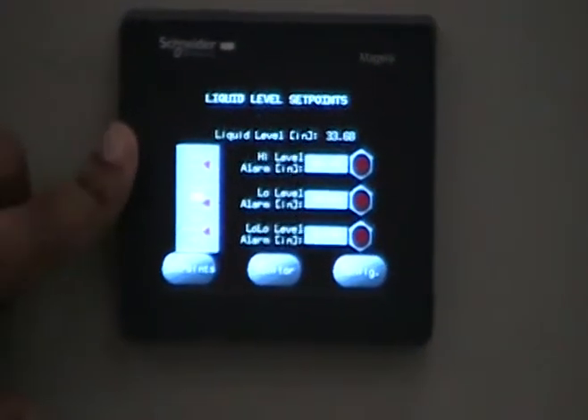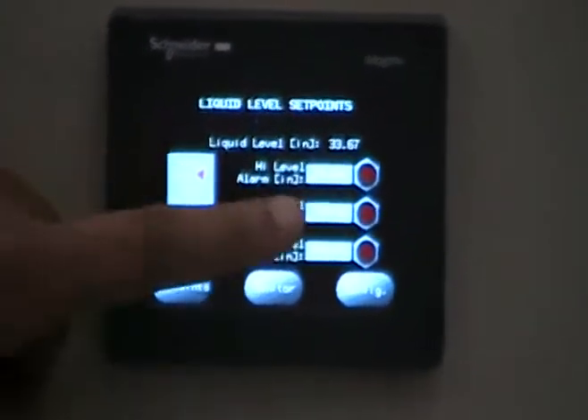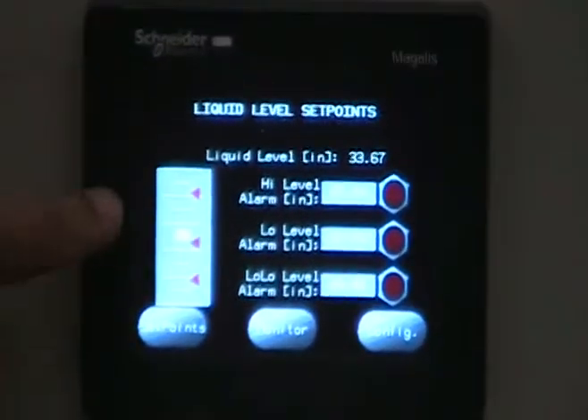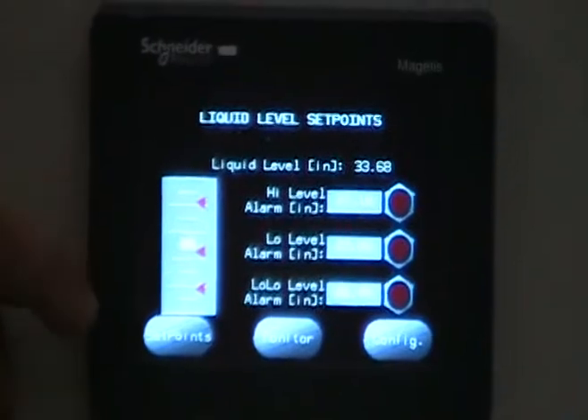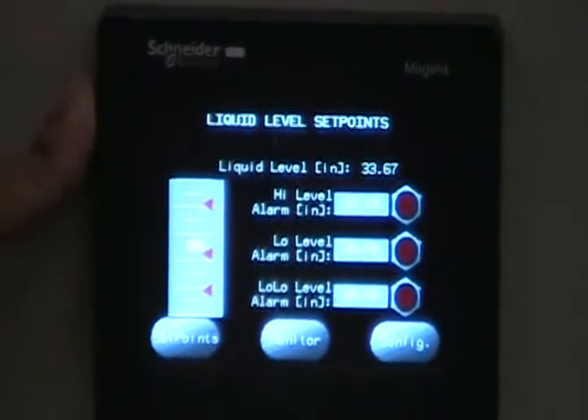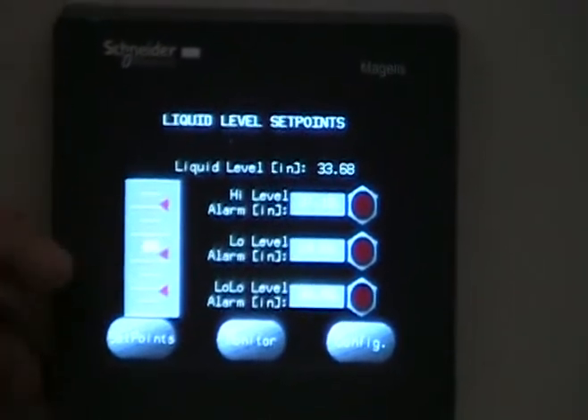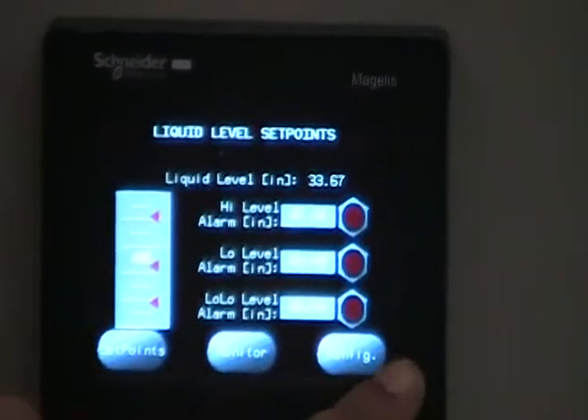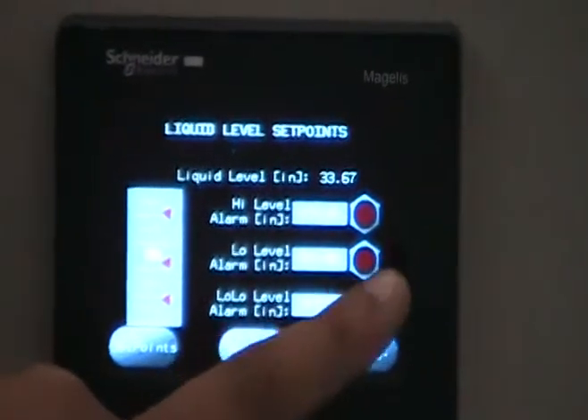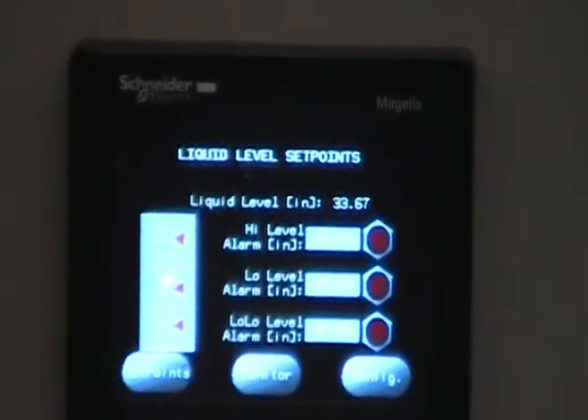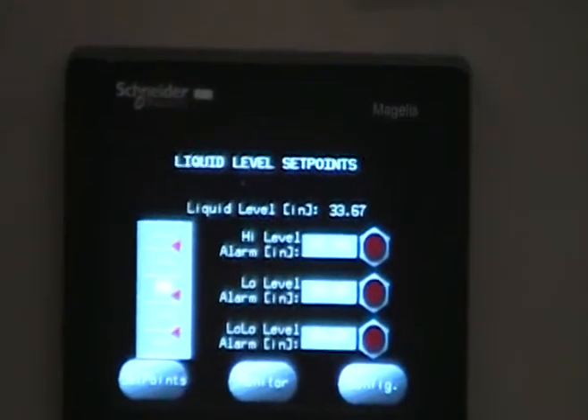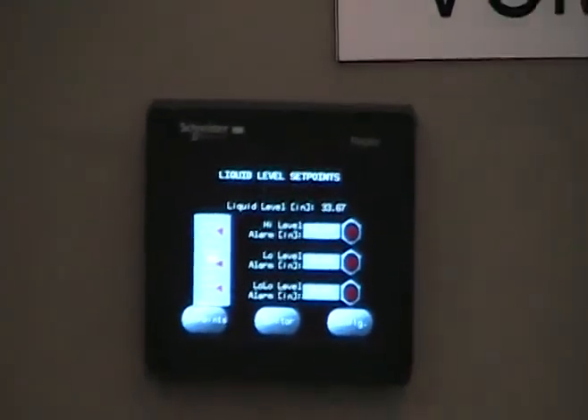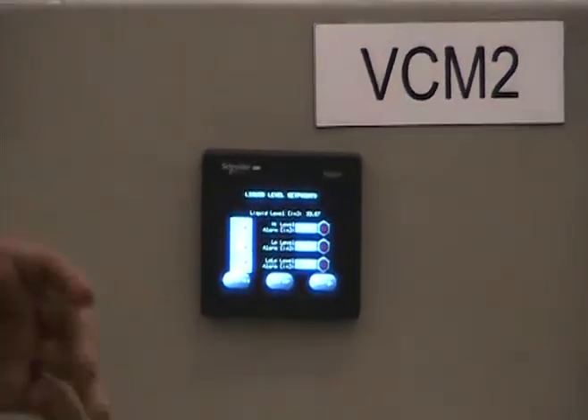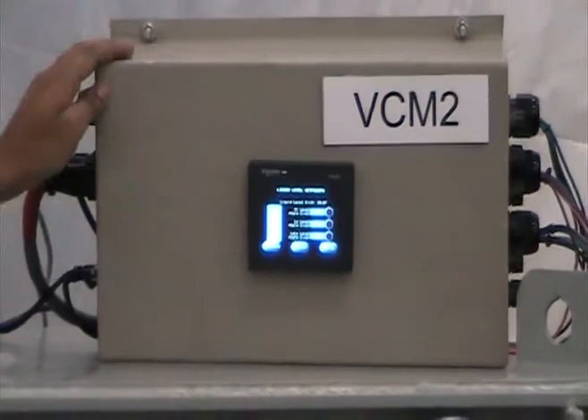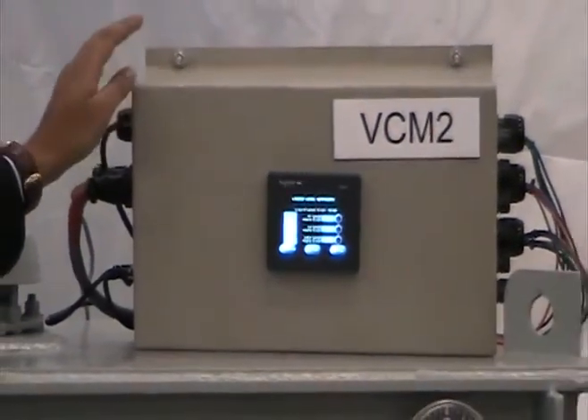Whereas in VCM, it provides the liquid level in inches. It provides the current liquid level in inches. There is also a physical indication on the screen as a graph display. Any change in the liquid level can be monitored using the VCM2. Alarm indications will be displayed for the liquid level reaching its set points. A major advantage of the VCM2 is that you can monitor the liquid level remotely. If the level goes down or up, we can adjust the settings before the alarm is activated. So, proactive maintenance is possible with the VCM2.